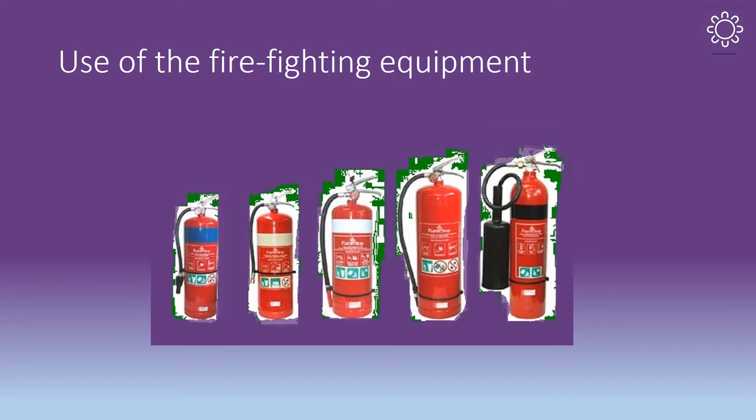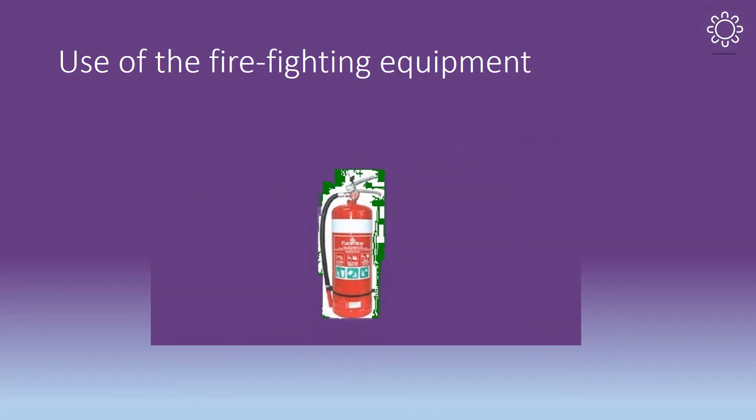All fire extinguishers within St Paul's Uniting Church are dry chemical fire extinguishers. Dry chemical fire extinguishers can be identified by a white band around the centre of the extinguisher. They contain a powdered substance that when discharged can be used on most classes of fire, including equipment that is connected to an electrical source.